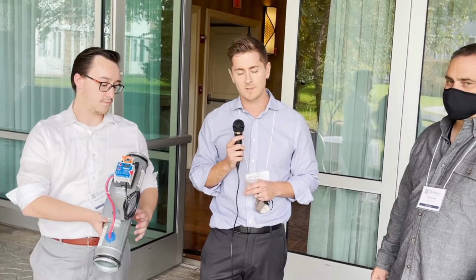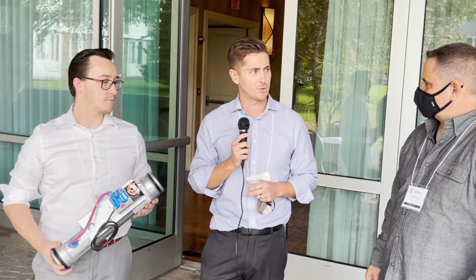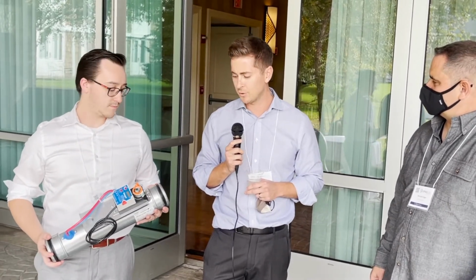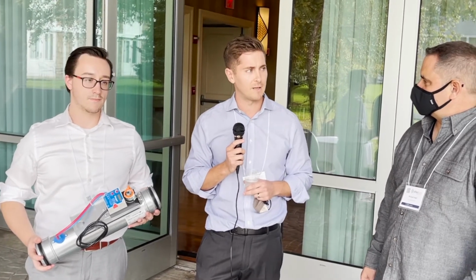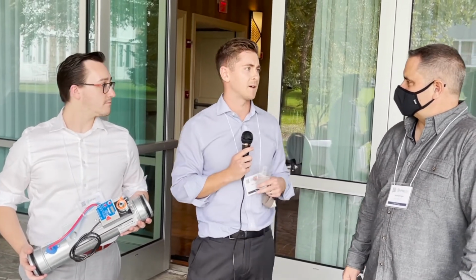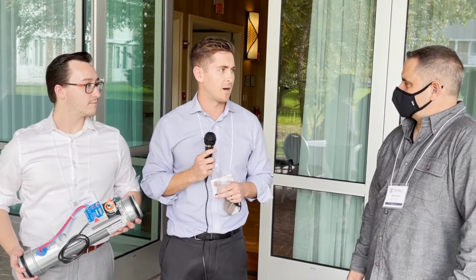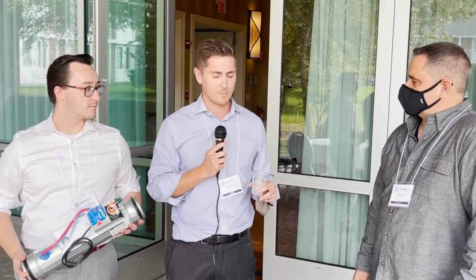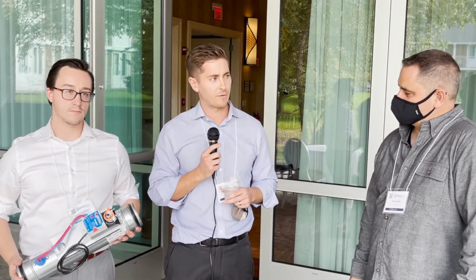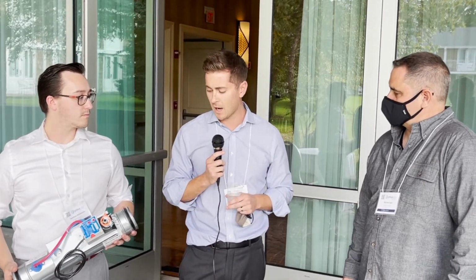In terms of a DCV, or demand control ventilation system, it truly gives you modulation in various spaces. Say you had a community space with a gym, and a lot of people went in at once - we can do boost mode, normal airflow mode, or setback mode depending on occupancy or CO2 levels in the space at a given time.